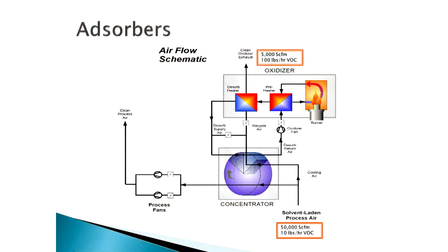This is just an example flow schematic of what that entire arrangement would look like. This particular schematic shows a recuperative oxidizer that has a primary and a secondary heat exchanger on it. The primary heat exchanger on this recuperative oxidizer is preheating the incoming gas stream, just like I showed you in the earlier slides of a recoup. And then we have a secondary heat exchanger that's creating the heat we use to send across the media and regenerate it. And that media is continuously rotating.